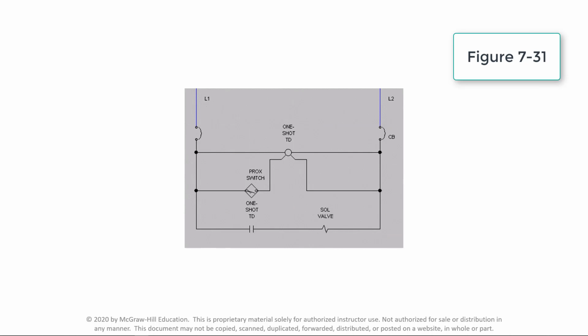This video demonstrates the operation of a one-shot timer circuit. One-shot timers are used when it is required to have an input signal of any time duration trigger a device or operation for a specified preset period of time. This scenario is an application of a one-shot timer used to energize a solenoid valve for exactly 10 seconds, regardless of the switching time cycle of the proximity sensor.